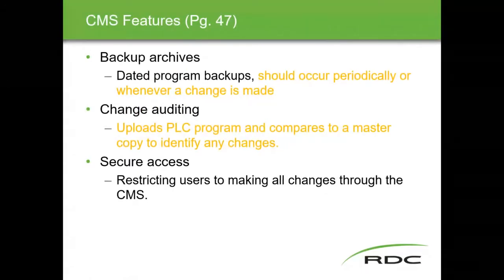Okay, some of the things that you can find inside of a change management package include backup archives, which contain dated program backups. Again, every time you sit down to do any type of work on the PLC system, you're going to back it up. Most places back up automatically at midnight anyway, but it's also good to do a backup before you do any work. So backup archives are one of the big features of change management.